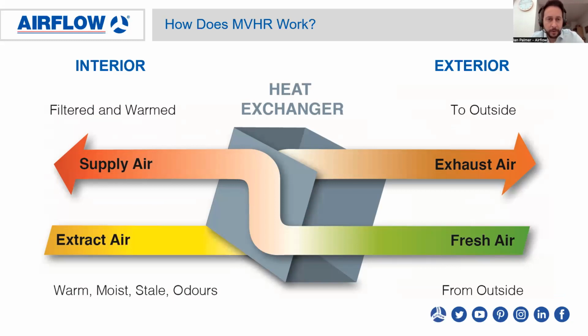So going on now to how heat recovery works. This is showing a plate heat exchanger, which is crossing over, so it's a counter cross flow heat exchanger. This works by extracting the air from the dwelling. The stale polluted extract air is put out into the atmosphere, and the warm energy is stored inside the separating fins of the heat exchanger. Then when the air is brought in from outside, it crosses over the heat exchanger. It's heated up by the stored heat energy inside the heat exchanger, and then it's supplied into the dwelling.